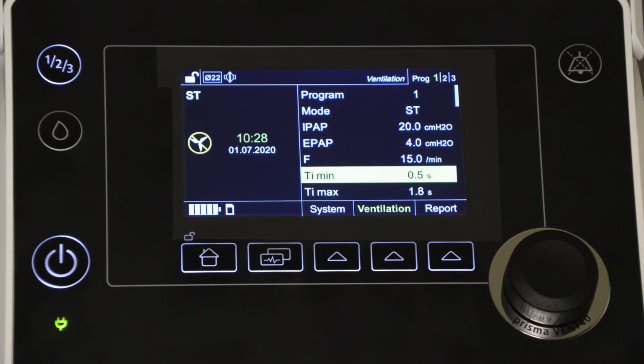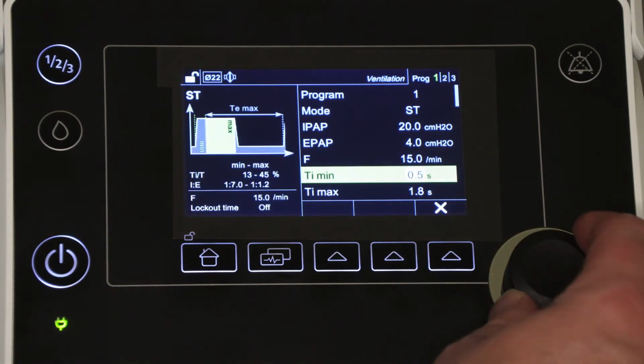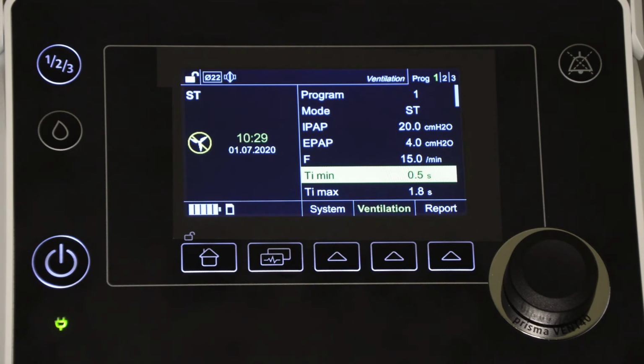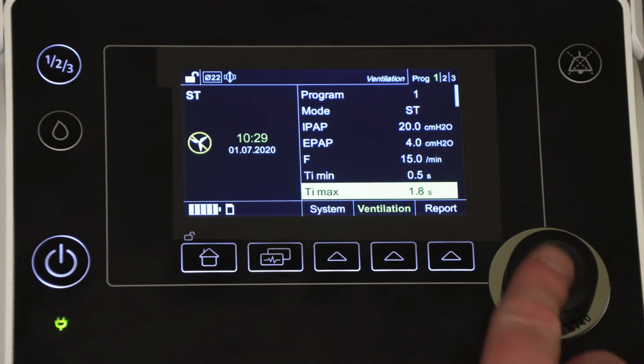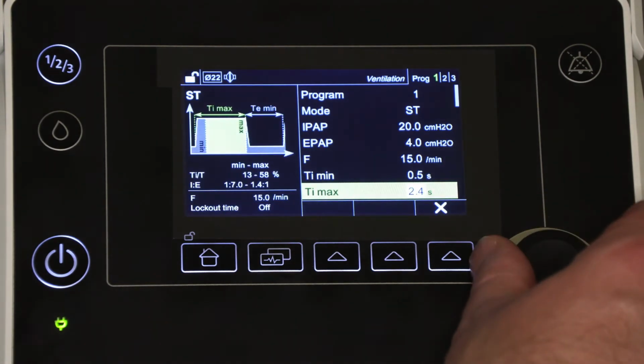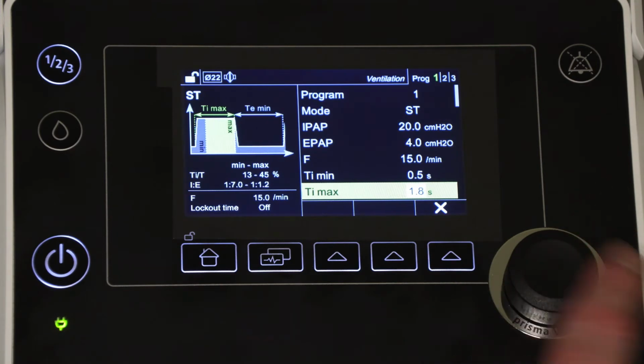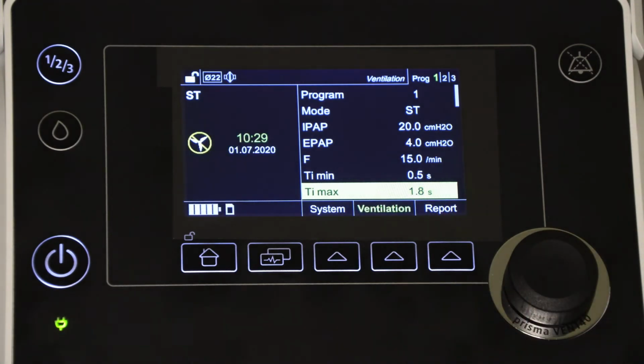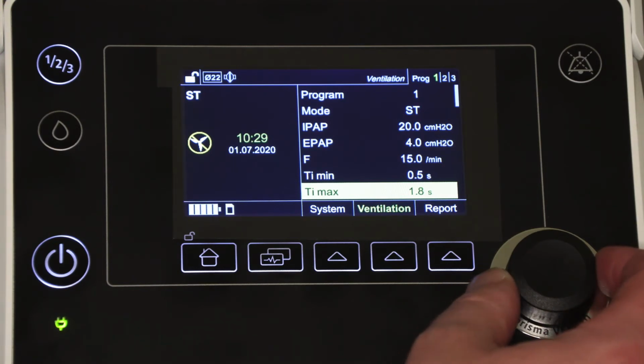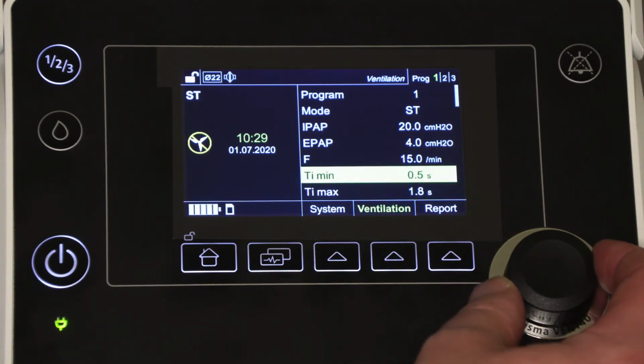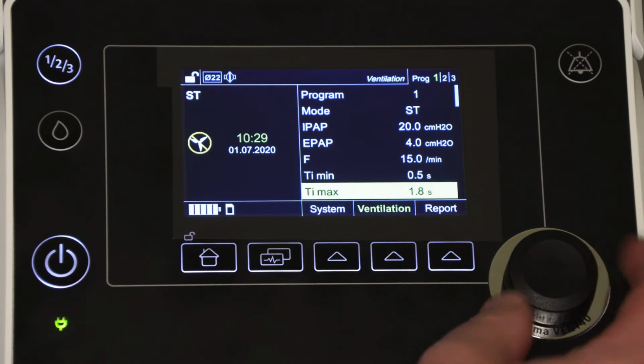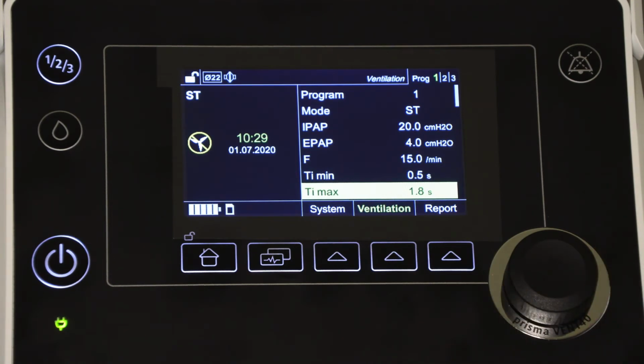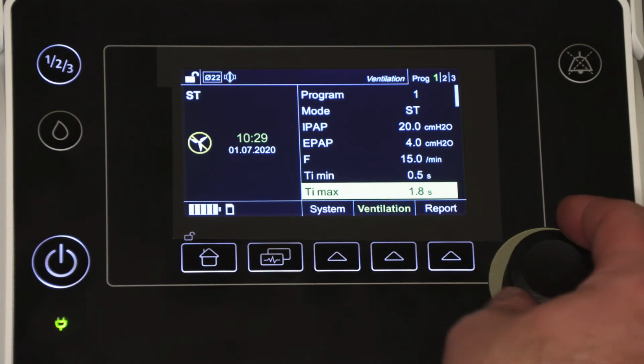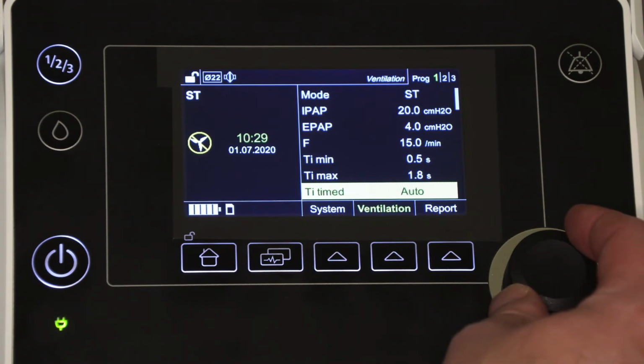The TI min will determine how short the inspiration is allowed to be, shown here as being set to 0.5 seconds. And the TI max will determine how long the patient's inspiration is allowed to be, shown here as being set to 1.8 seconds. This means that the patient's triggered inspiration from the ventilator can be anywhere between 0.5 and 1.8 seconds, or anywhere between whatever these two values are set to.